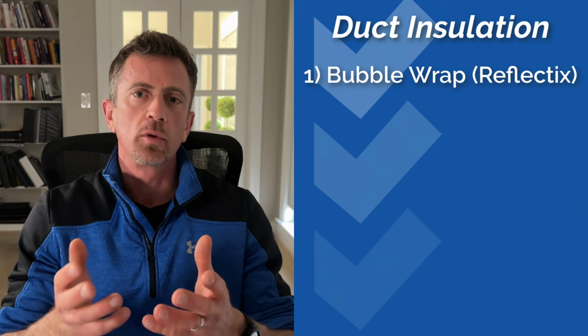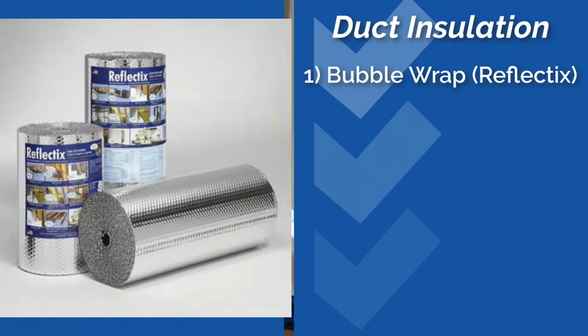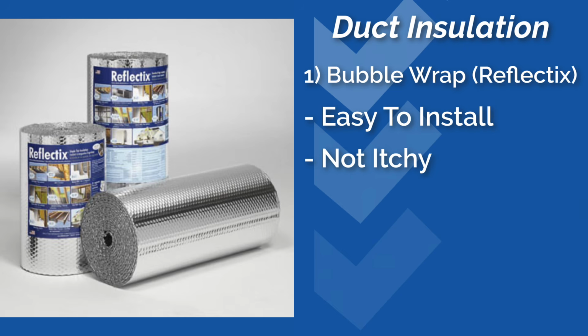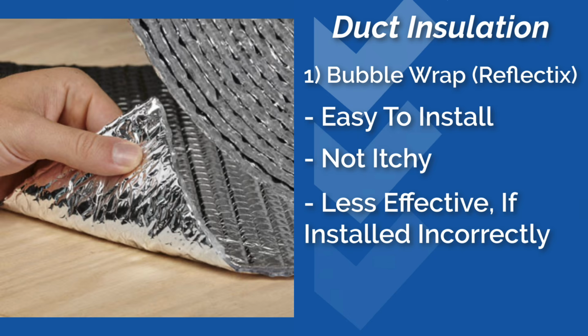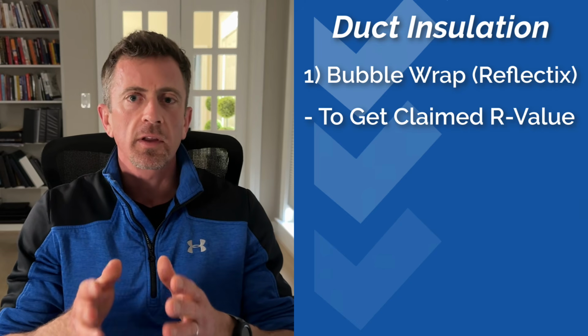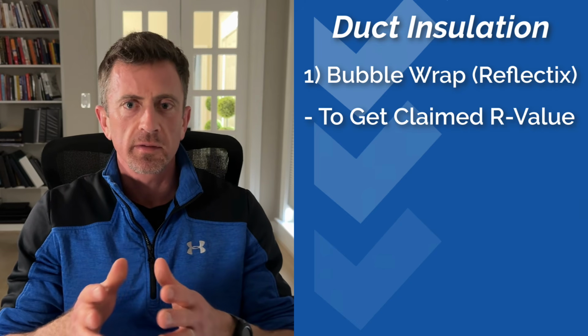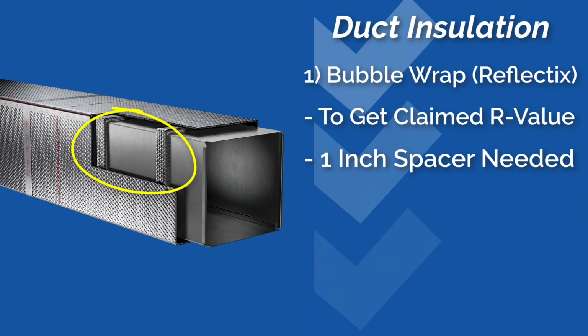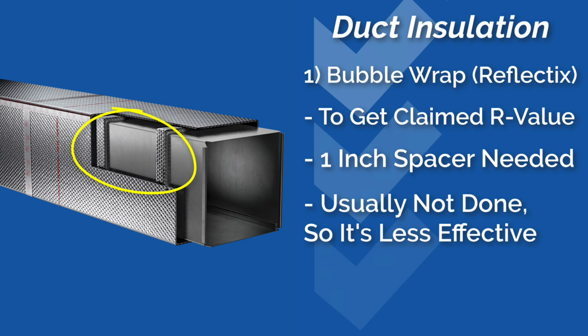The first one is bubble wrap or Reflectix insulation. It's easy to install and it's not as itchy as fiberglass, but it's also less effective if it's not installed correctly. In order to get the claimed R value from the Reflectix, you need to have a 1-inch airspace between the duct and the bubble wrap itself. And most people don't do this, so it's usually not very effective.